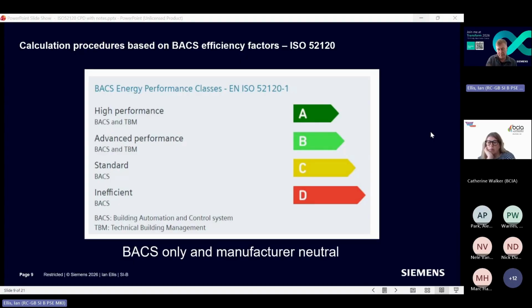The standard recognizes that, which is good for us, because we tell people that's what you should do, but also good for installer companies and systems houses, because it can help justify why you need proper service and maintenance regimes, why if you're collecting data you really need to analyze it properly and use that to drive performance. And Class A, again, uses the BACS and TBM, but it goes into a bit more detail, or requires a bit more control.